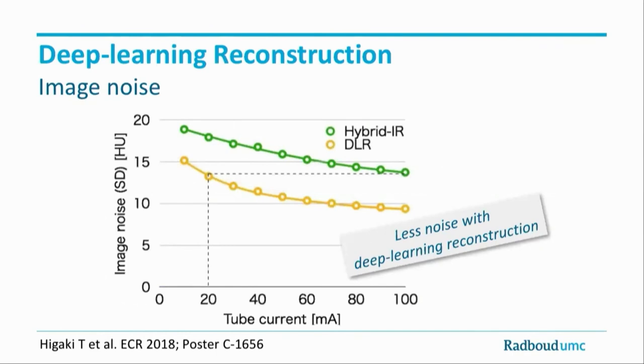Measurements from a Japanese group show that the image noise with deep learning reconstruction is the same as with hybrid reconstruction at five times more dose — 100 mA tube current produces the same noise as 20 mA with deep learning reconstruction. Does that mean we can reduce image dose by a factor of five? Unfortunately no, because although measured noise as standard deviation is the same, the noise texture changes and becomes much rougher. However, we can still reduce the dose by roughly 30% and get a better, finer noise texture at that lower dose.